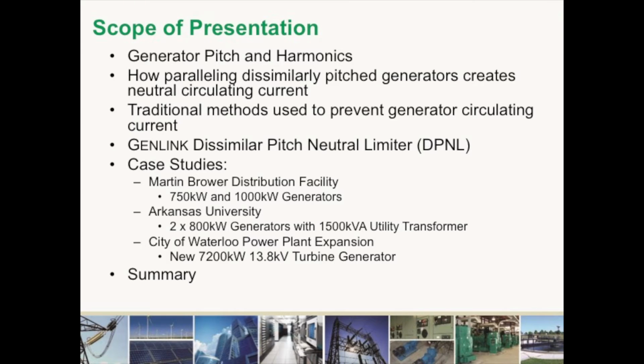So today we're going to be talking about generator pitches, the configurations of generators, and how that can result in harmonics. We're going to look at paralleling dissimilarly pitched generators and why that creates neutral circulating current. We'll look at a few traditional methods to prevent generator circulating current. And then I'll introduce the GenLink DPNL, which is an easily applied unique reactor for blocking the circulating currents. And then we'll review a few case studies of applications that we've done.